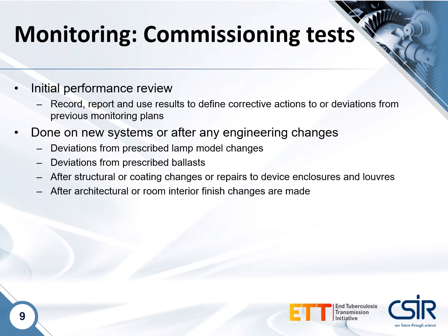These tests are done not only on new systems, but also after any engineering changes. These engineering changes could include deviations from specified lamp models or deviations from prescribed or specified ballasts. They should also be done after structural changes to any UVGI device, that is, changes or repairs to device enclosures, device louvers, or any changes to the coating, that being repainting or refinishing of the device. In addition to that, performance review testing or commissioning testing should be done after any architectural change or changes to the interior finish of the room in which they are installed.